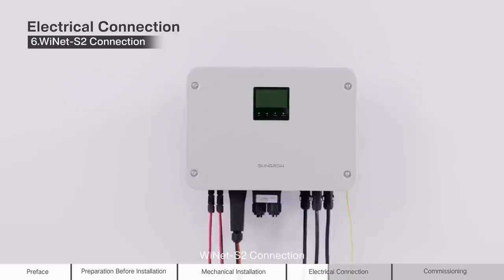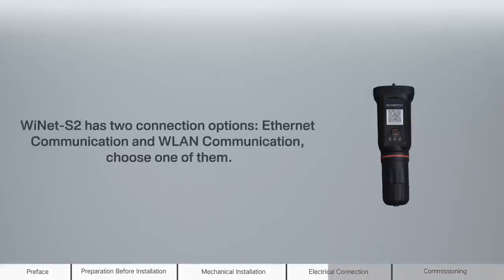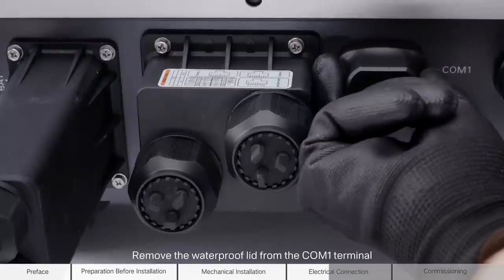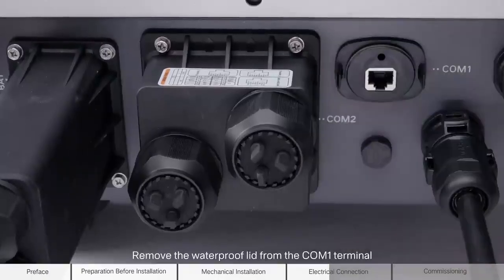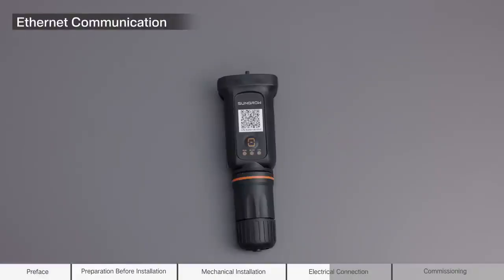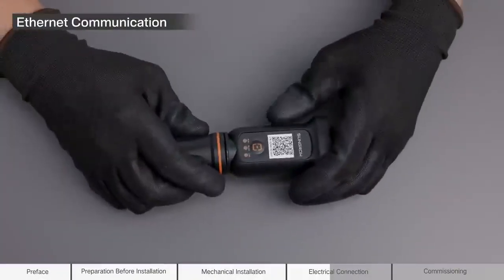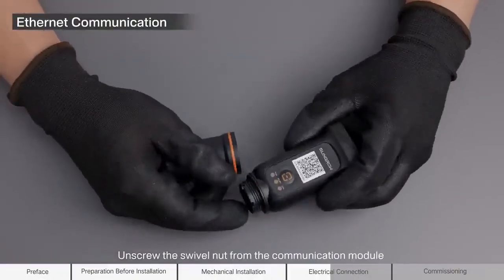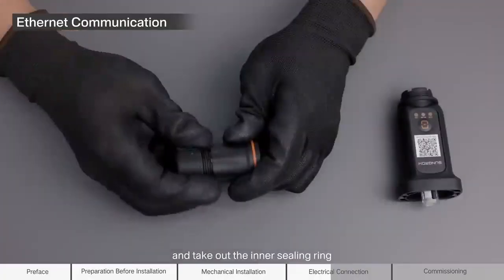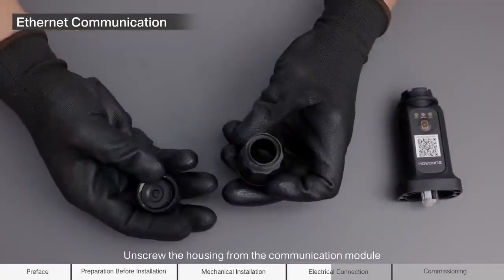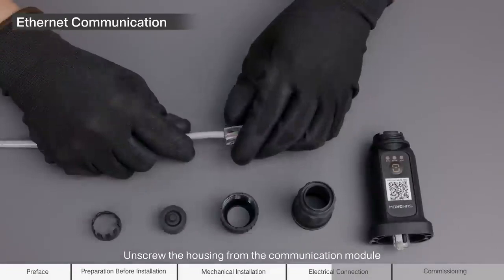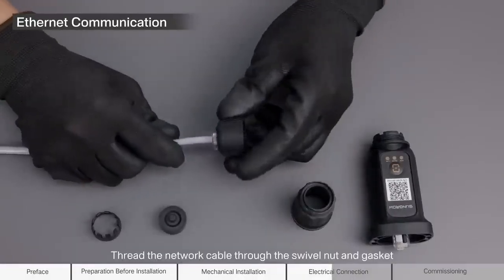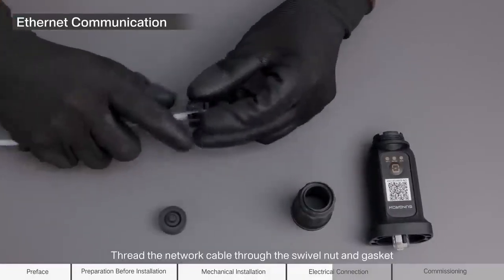6. WiNet-S2 connection. Remove the waterproof lid from the COM1 terminal. Ethernet communication. Assemble the Ethernet cable. Unscrew the swivel nut from the communication module and take out the inner sealing ring. Unscrew the housing from the communication module. Thread the network cable through the swivel nut and gasket.